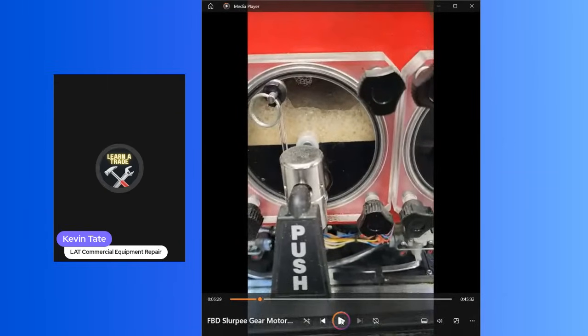So I just shut it off. That was just to confirm what I suspected was happening, that the beater motor is bad and needs to be replaced, because when it freezes down, that beater motor is going to stick. It's not going to turn correctly, and eventually it will cause the unit to shut down.